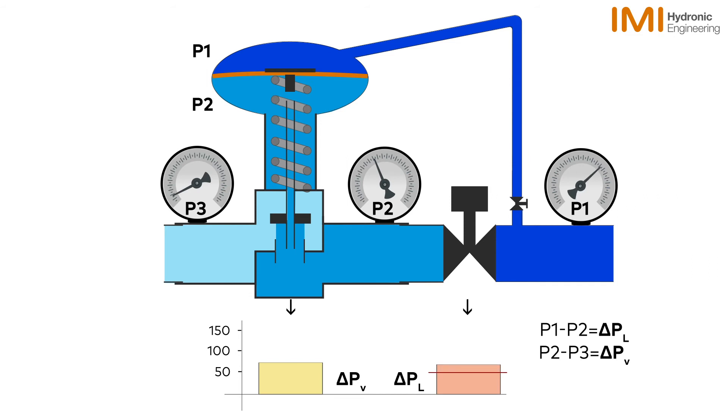As we can see, the DPCV will constantly see a change and act upon it as P1 to P3 is increased. It is able to accurately control delta PL until such a time as it reaches the minimum opening.